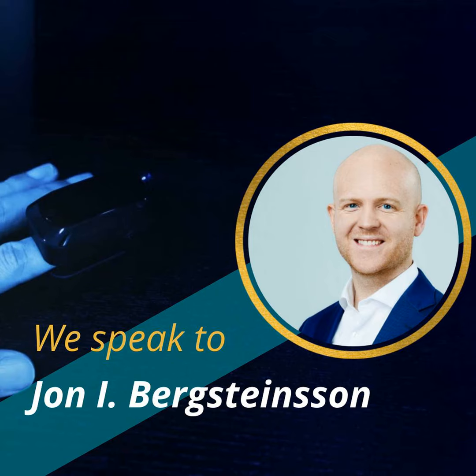new products to market. This also impacts existing devices in the market, because the new medical device regulation in Europe, and I would primarily talk about the European impact here, the new medical device regulation in the European Union requires that all medical devices are recertified according to this new regulation. So there's no so-called grandfathering of existing devices. Existing devices won't get a free pass.